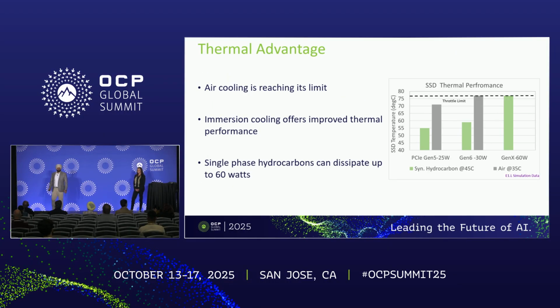Next, we're comparing SSD thermal performance in an air-cooled environment versus an immersion-cooled environment. At 25 watts, yes, there's margin in an air-cooled environment. In a typical data center at 35 degrees Celsius with typical fan flow, you don't need to run fans at higher speed to cool a 25-watt SSD. This immersion data is based on simulation, one of the worst form factors, and it still has a lot of margin. Going to the next generation, say 30 watts in Gen 6, you still have a lot of margin with immersion, but air cooling is hitting its limit.